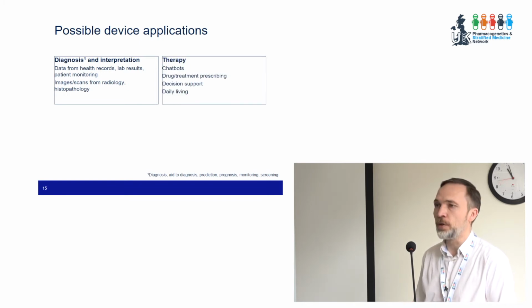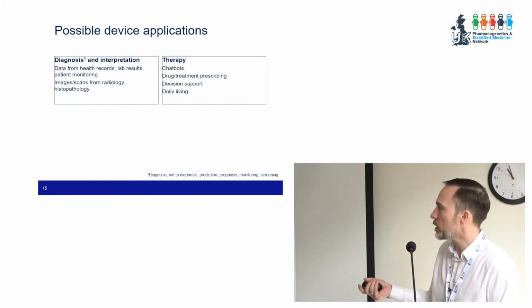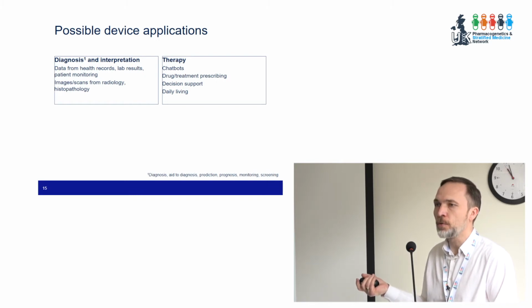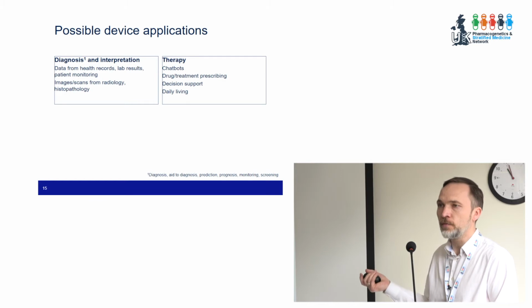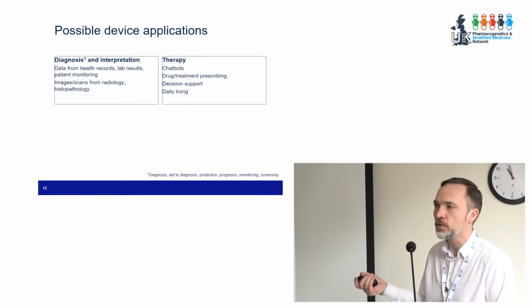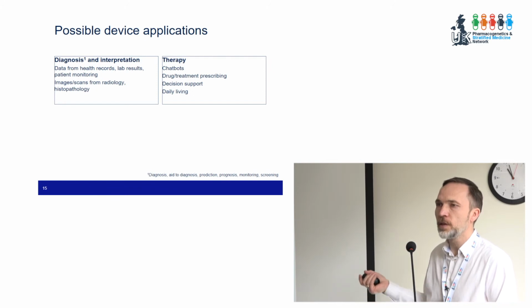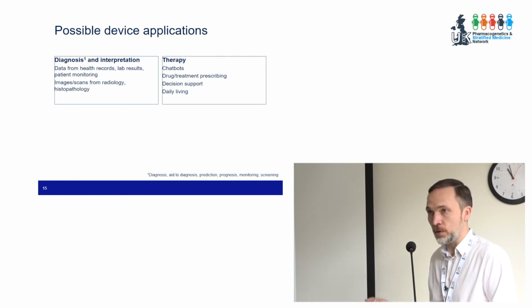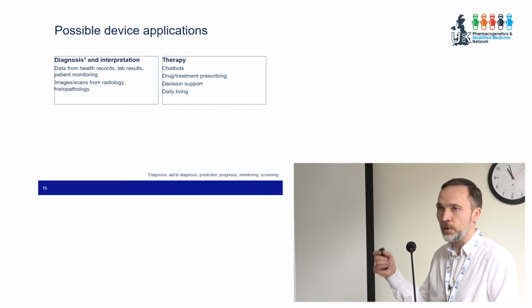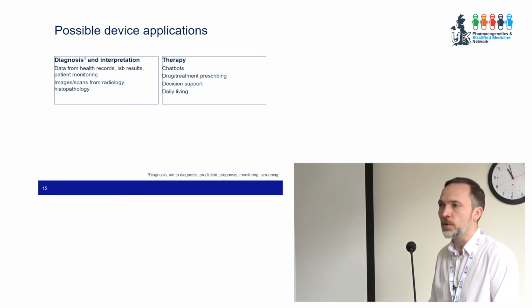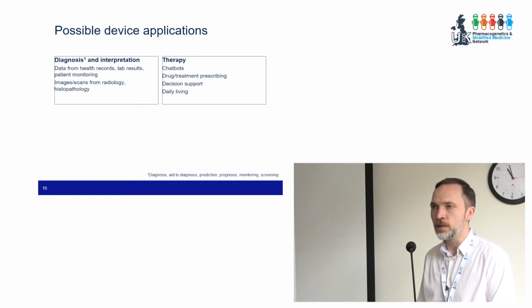We see software being used in therapy. So a chatbot delivering cognitive behavioural therapy could be, and by the way, this doesn't have to be done within the UK. The product providing this service might be in the US or China. Now there is a distance sales provision which says if you're providing that service to the UK, to the EU, then that product still needs to meet the requirements of the regulations. So you can stick your product on a server in the US, it still needs to meet all of the requirements.